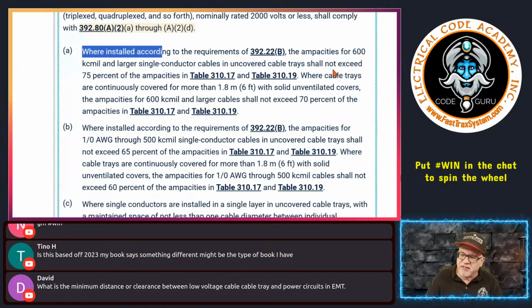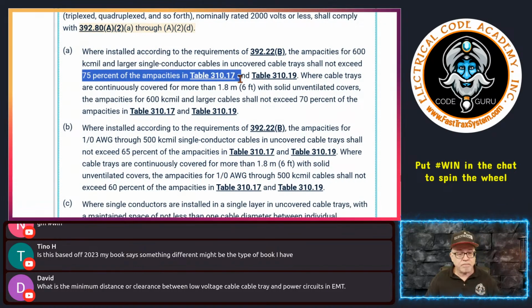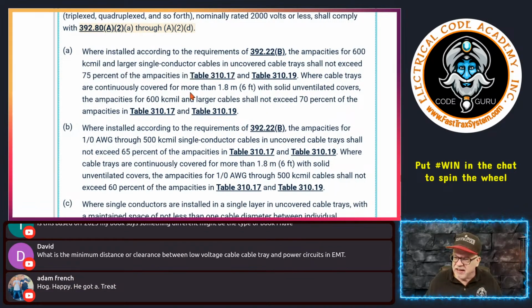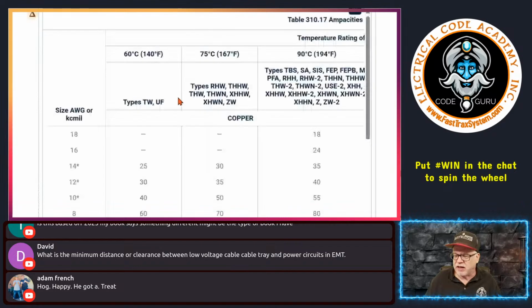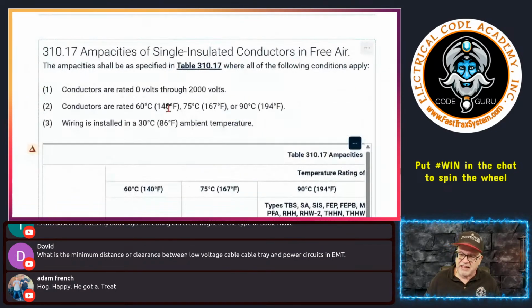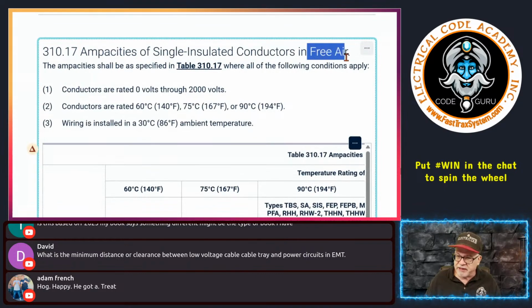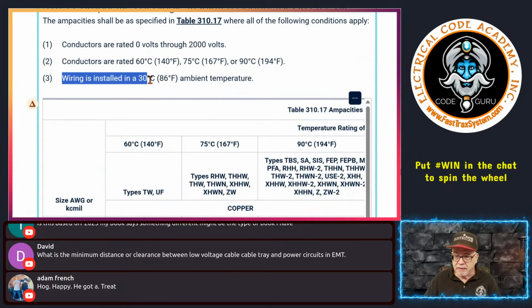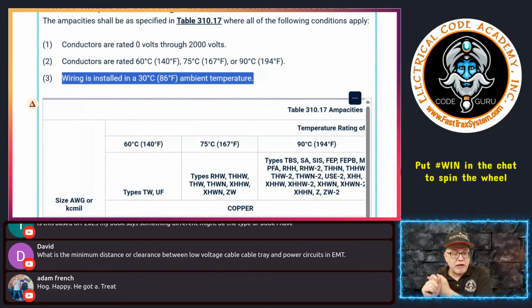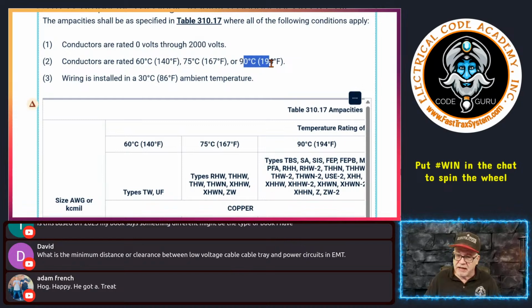It says the ampacities shall not exceed 75% of the ampacities in Table 310.17. Now here you go. So why is this not using 310.16? Because you're able to use the benefits of 310.17. If I click on it, you can see that 310.17 is about ampacities for single insulated conductors in free air. So they're allowing you to utilize the ampacities here rather than 310.16. Again, I'll remind you, this table, just like 310.16, is based on 30 degrees C, 86 degrees Fahrenheit. You'll notice that the conductor insulations are the same, 60, 75, and 90. Everything else is the same.